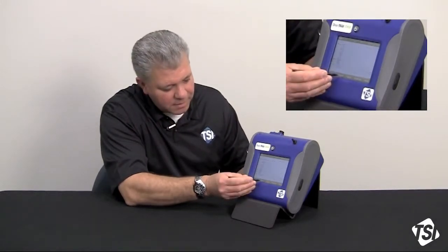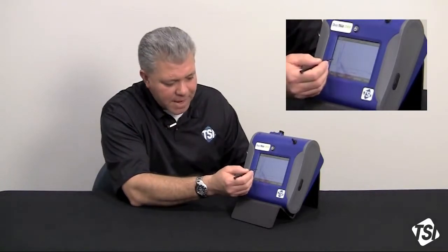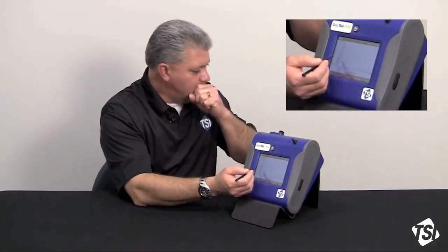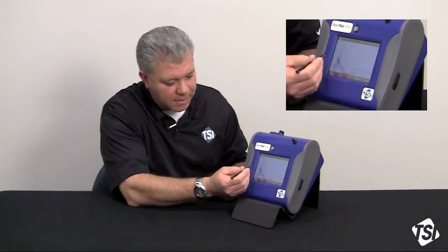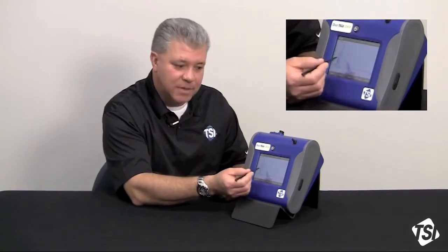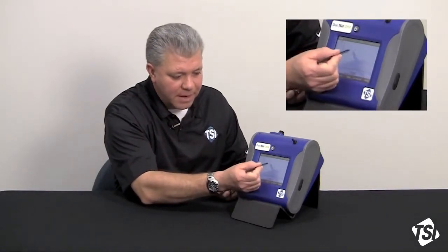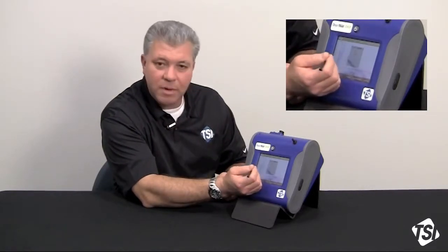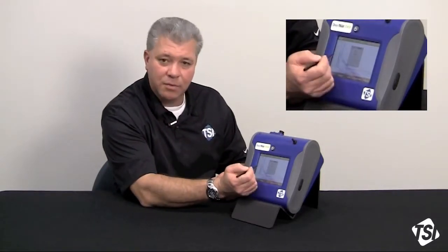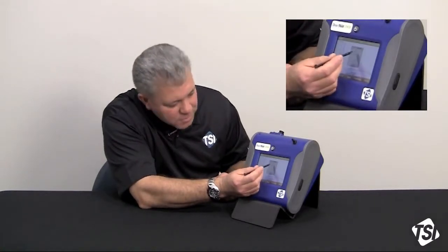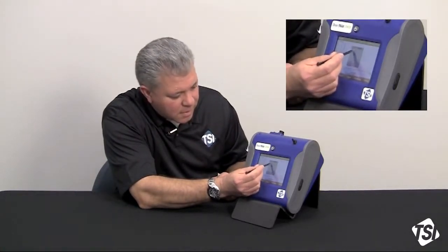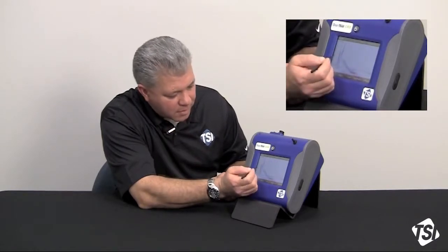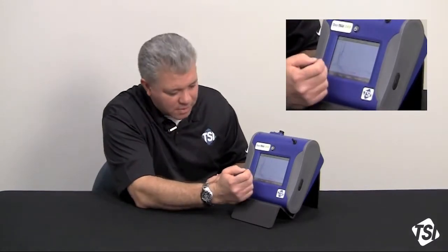Now here's an interesting thing to look at. We have the ability to look at a real-time graph of data. What you will see is a 5-minute rolling average that goes across the screen. I also have live keys here. If I go up into this area and touch in here, I can look at, do I want an average or a TWA line through my data? And I'm just going to select average. Going to highlight that, click OK, and now I'm going to get an average concentration line.